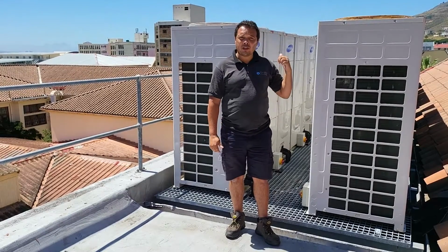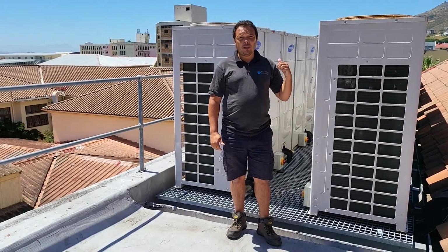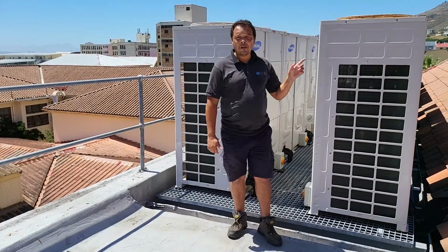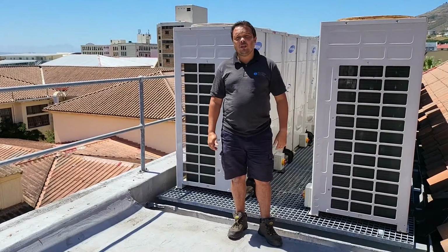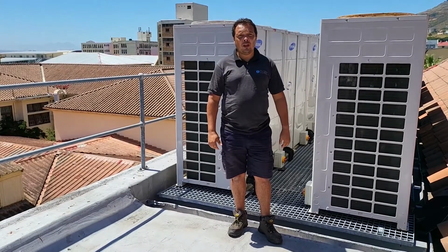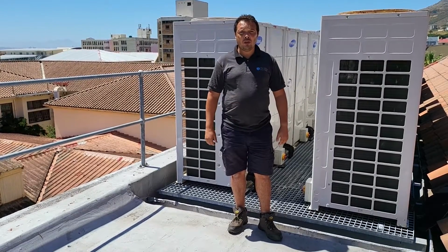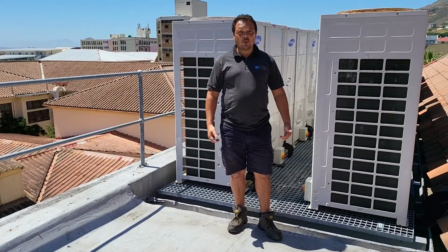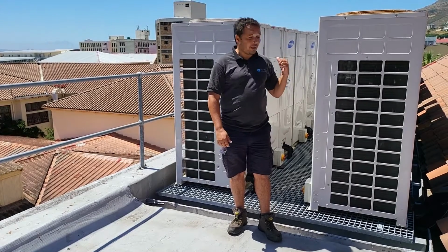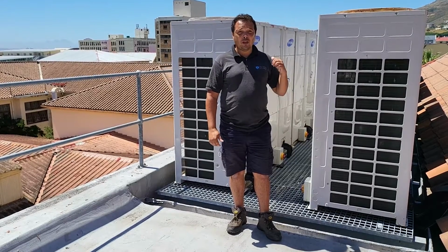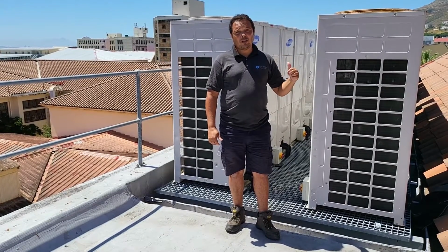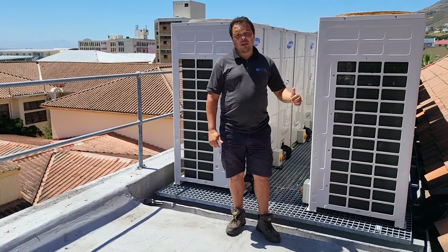The system they've asked us to look at is a two condenser system, DVM S Samsung. According to the addressing on the condensing unit, we have 19 indoor units as well as 4 MCUs. Unfortunately, because we didn't do the installation and there isn't an active or available schematic for the system, we're going to have to physically go in there and check out exactly what's happening, how many MCUs, and see if the numbers are correct.